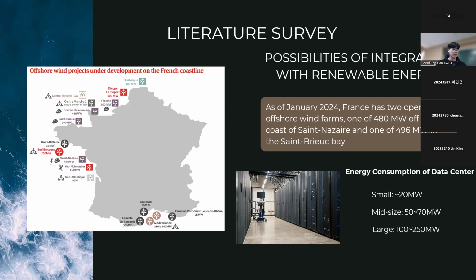A small size data center has power consumption up to 20 megawatts, while a mid-size facility can consume between 50 to 70 megawatts, and a larger one can be from 100 to 250 megawatts. Meanwhile, the largest offshore wind power generator has a power generation capacity of well over 500 megawatts. In other words, this figure is sufficient to cover data center power consumption.